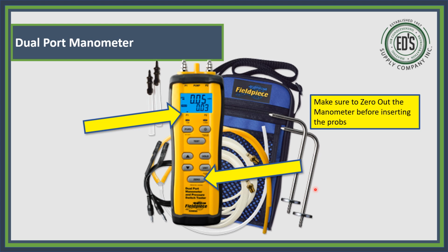So I'm going to take the clear tubing on these manometers. I'm going to put it here. There's my P1. There's my P2. This is P1. That's P2. So right now, this manometer, see that little dot under P1? I'm reading what's off this would be in my return. And let's say it's showing me that I have a 0.03 and then I have a 0.05. Now, here's what happened. This should be your total. I may be wrong. This may be the total and that may be it, but you'll see the numbers when you pick.